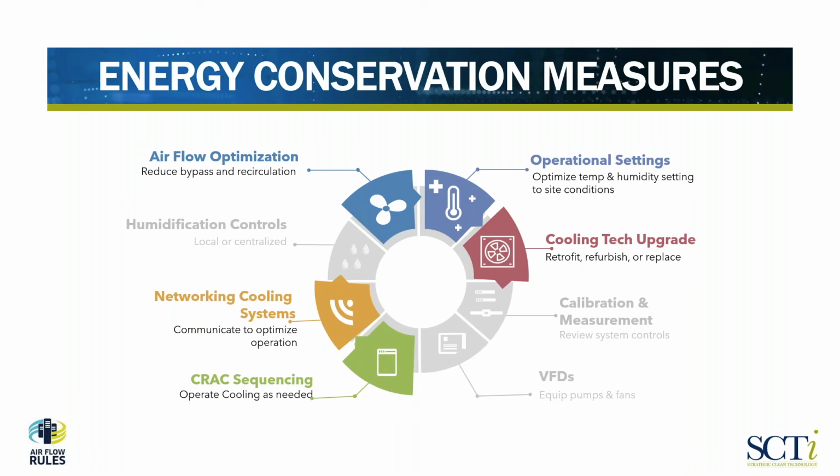The airflow optimization, it's not just management, which to us is the separation of cool air and warm air in the data center, but it also takes it a step further and goes into the optimization. How much air do I need going to my IT equipment so I can, again, meet the definition or objective of cooling optimization, being the proper amount of cool air going to the IT equipment.